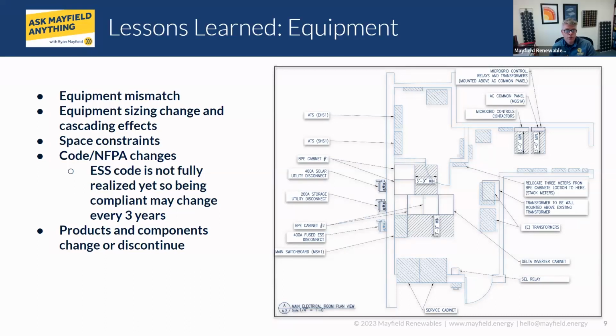Yeah, the listing aspect is really important, and 9540A, having that testing and being able to get it from the manufacturers, is an important one. That's something I've talked about quite a bit when we got into codes and standards. As of now, 9540A will be an absolute requirement relatively soon, as the newer 855 is adopted throughout the US along with new fire codes. But right now it's still something you have to go out and get and interpret yourself, so that's an important one.